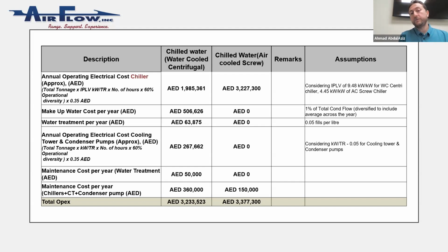Then your makeup water, you have an additional 500,000 for water cooled. Then the water treatment per year, an additional 63,000. Then the annual operating electrical cost for cooling towers and condenser pumps, because this is only for water cooled, another 267,000. Then the maintenance cost per year for water treatment, another amount. Then the maintenance cost per year for chillers, cooling towers, and condenser pumps, 360,000 for water cooled, 150,000, almost half, for air cooled. If you do this OPEX summation, you will get 3.2 for water cooled chillers, and 3.3 for air cooled, almost equal to each other.